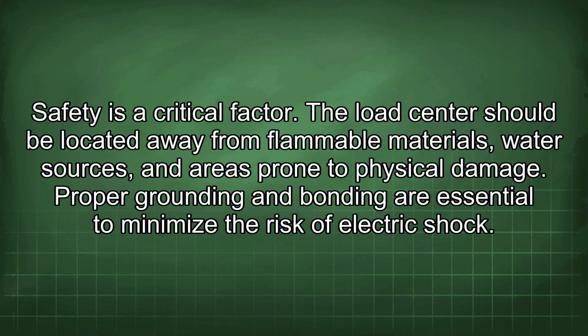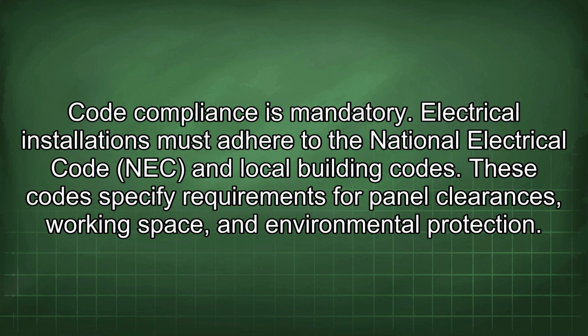Safety is a critical factor. The load center should be located away from flammable materials, water sources, and areas prone to physical damage. Proper grounding and bonding are essential to minimize the risk of electric shock. Code compliance is mandatory. Electrical installations must adhere to the National Electrical Code (NEC) and local building codes. These codes specify requirements for panel clearances, working space, and environmental protection.